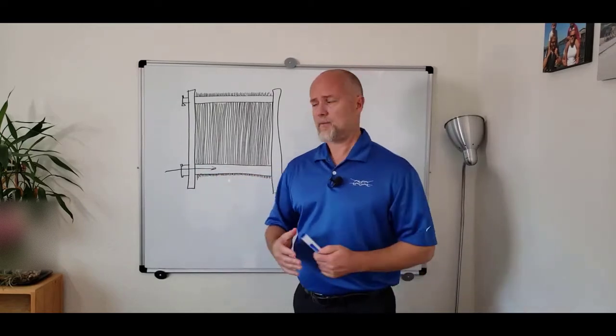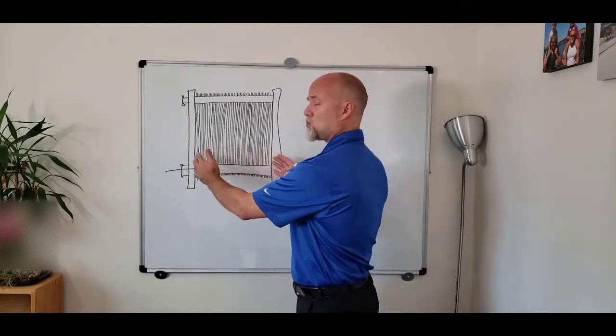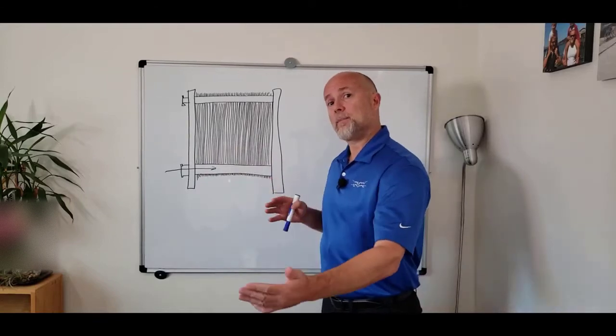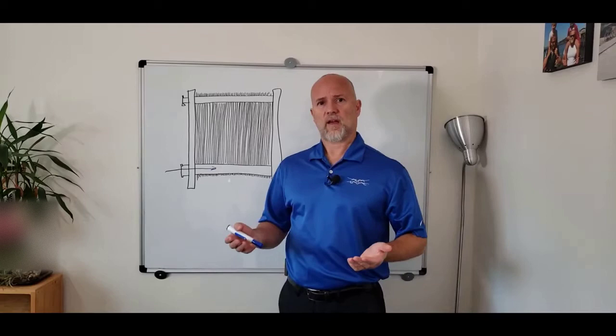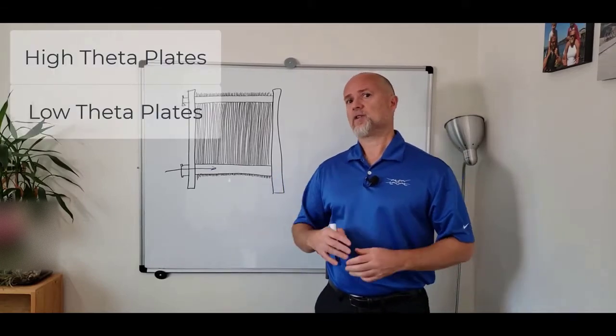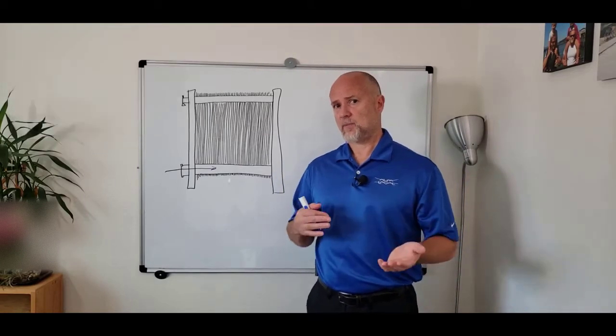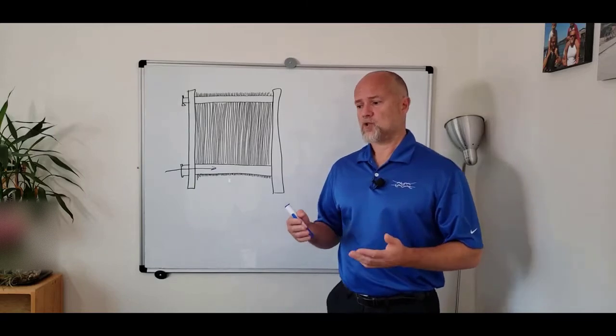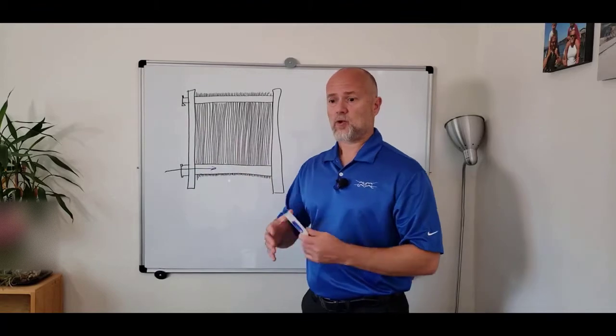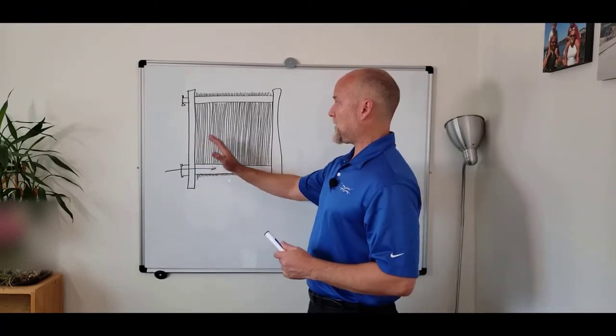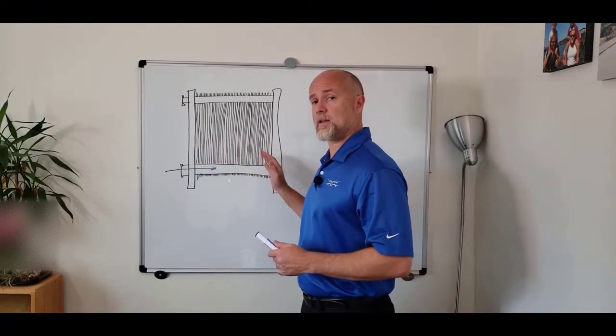The first challenge that you have is to have an even distribution throughout the plate pack, which means that you might remember that we have high theta and low theta plates that have different pressure drops. So you want to stack your plates in a way that does not have an uneven distribution throughout the plate pack.